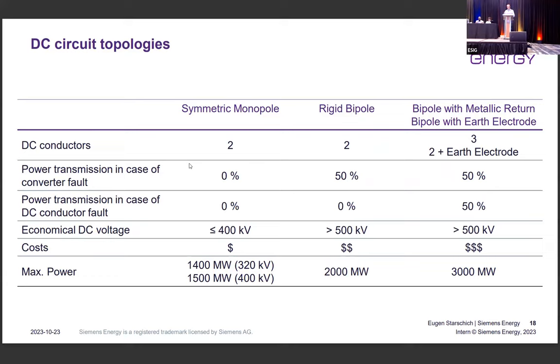What we're looking at: symmetrical monopole, rigid bipole, bipole with metallic return, or bipole with electrode, summarizing the availability. As I said, symmetrical monopole is the cheapest solution you can think of, but it has no redundancy. The maximum DC voltage used in this configuration is plus minus 400 kV. There have been a few projects under execution or being built with this DC voltage. The most common voltage is 320 kV, and the resulting maximum power is 1400 to 1500 megawatt.